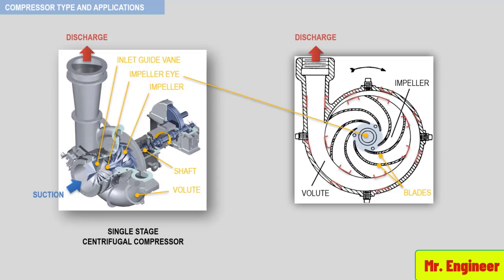The principle of operation of a centrifugal compressor is very similar to that of a centrifugal pump. The gas to be compressed enters the compressor through the inlet nozzle or suction nozzle. The gas is then directed into the eye of the impeller. The impeller is attached to a shaft. The shaft spins and is powered by a driver, which is not shown here. The gas, once it enters into the eye of the impeller, is trapped between the impeller blades. The blades contain the gas and impart speed to it as it passes from the impeller eye toward the outside diameter of the impeller.